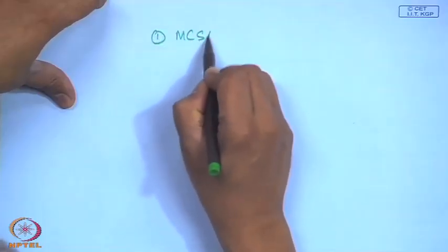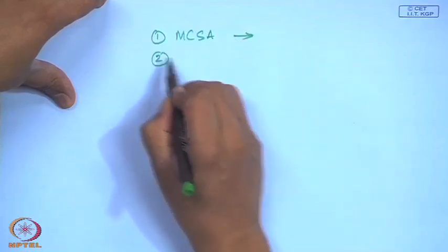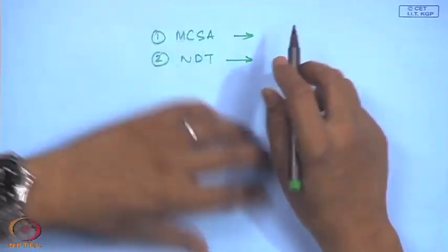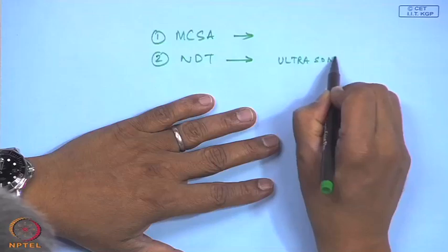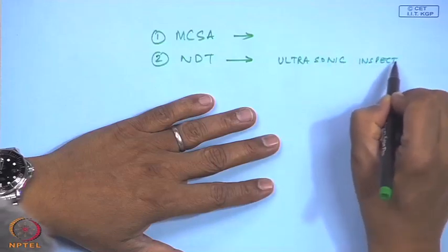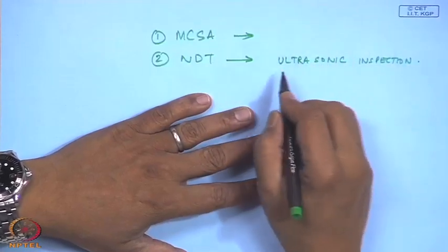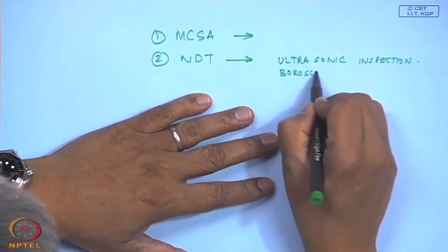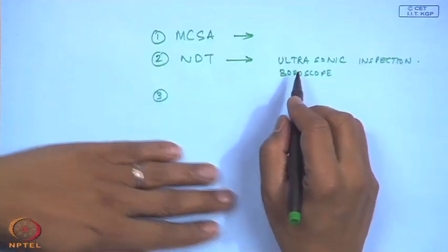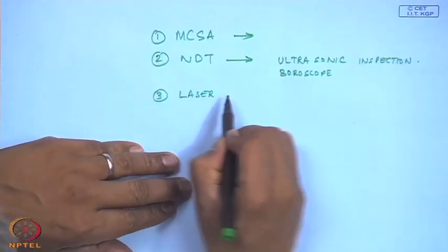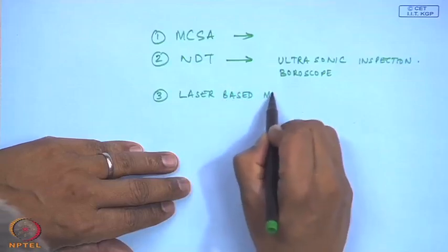So, that is why MCSA has become a good candidate. Next, we can use a lot of the NDT techniques. Of course, NDT techniques cannot be real time, but it is a good practice. Particularly for gas turbines or turbines, we can do a quick ultrasonic inspection. The internals of the turbines can be looked at through visual inspection, boroscoping.